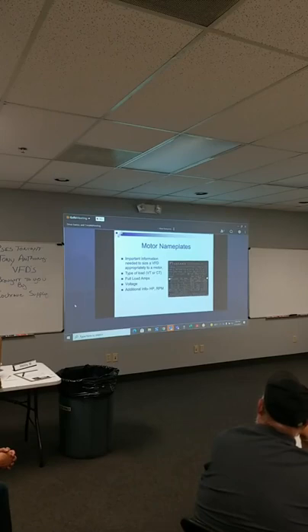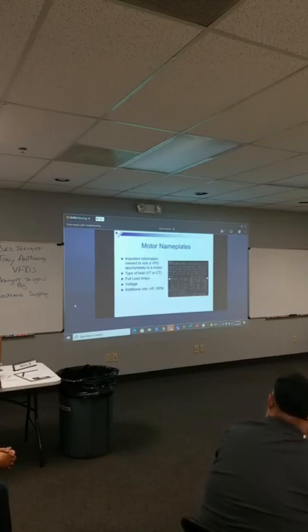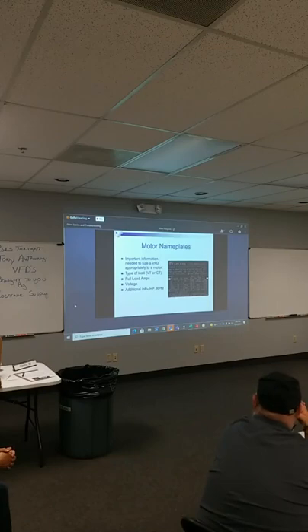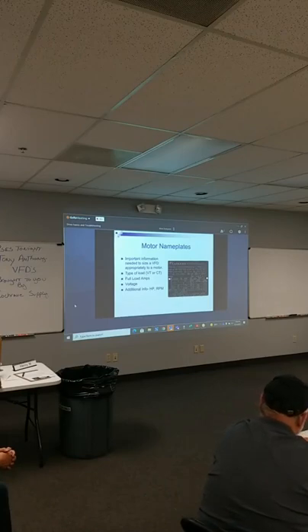They were a special low RPM motor. When we saw the motors, to size the drive to handle that 125 horsepower, severe duty, low RPM motor, we needed to go all the way up to 175 horsepower. The problem was those drives were already sitting there. Without that paper trail, it would have been my distributor's issue, or the contract's issue, but we had to pay for it. We were begging the engineers for the information and they never got it to us. It was on them. So, full load amps, all that to say, whoever said full load amps, thank you. That was perfect.